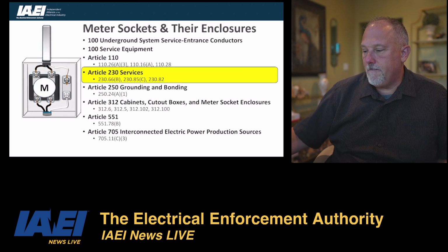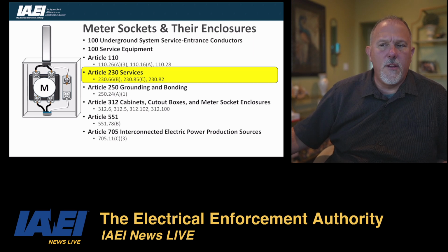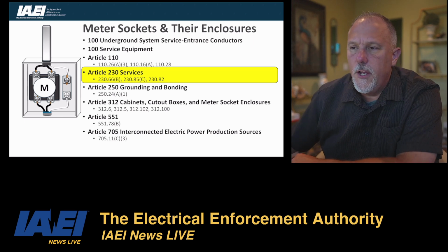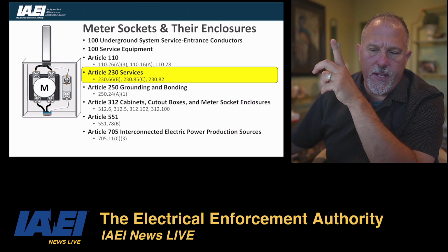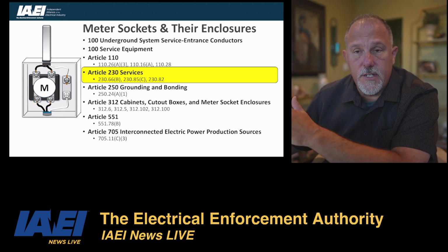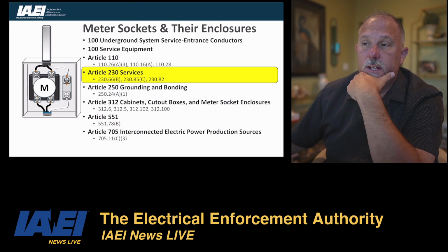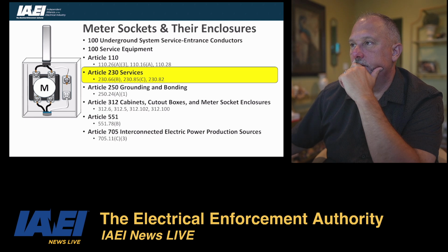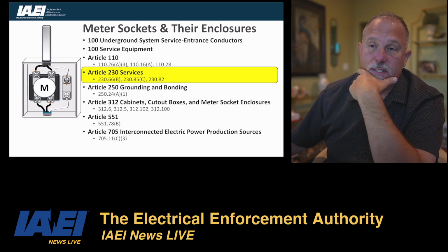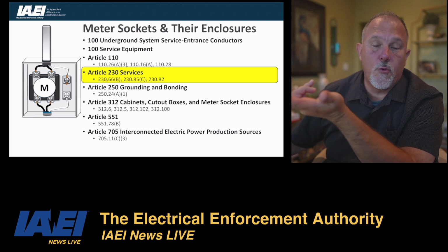So that's your 110.16. And also in 110, you've got to, again, think about all the different areas. So all of 110 applies, right? You have your terminations, your electrical connections, 110.14 requirements, torque requirements. Your arc flash label for service equipment, not for the meter socket itself, but if your service equipment is a meter breaker deal, then that piece of equipment will have to have that arc flash labeling. 110.22, identification of disconnecting means. 110.24 will be your available fault current. 110.26 is spaces about your electrical equipment.